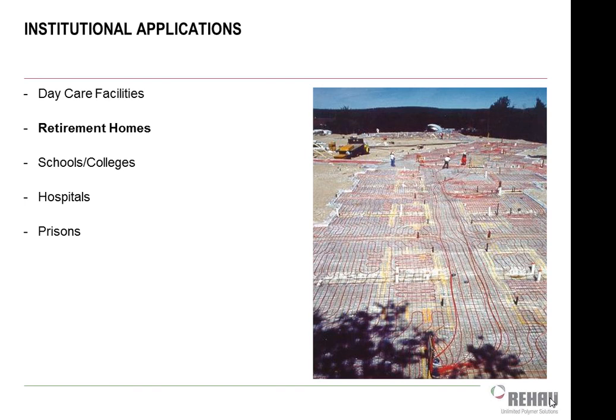Retirement homes, very popular for radiant heating. Those folks are always cold. Radiant heating helps warm their body as opposed to the air around their body, so they tend to feel comfortable. Hospitals are very popular as well. Once again, with the ability to reduce the amount of air moving around, we can filter less. We still have to bring plenty of outside air in for ventilation reasons, but if my ventilation system is only 40% of my otherwise air side system, that's a lot less I have to do on the filtration side, and the filtration levels in hospitals are pretty high, so doing as much as I can with radiant not only saves the energy, but it also reduces how much I have to buy and change filters and things like that.